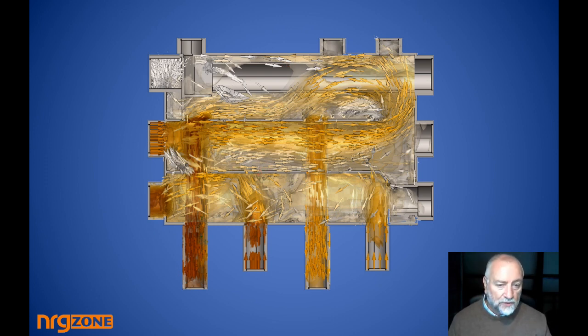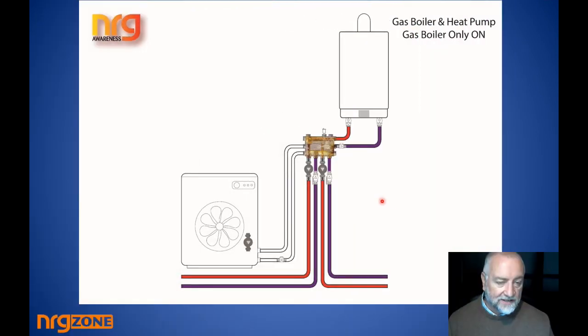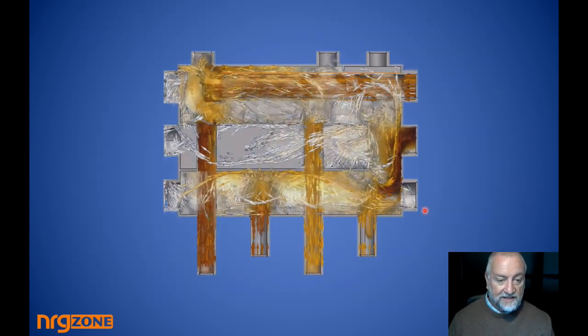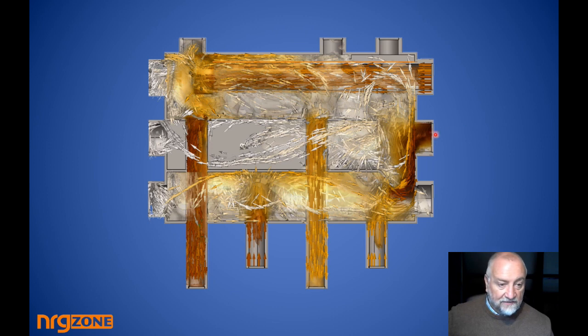If we go to the next scenario, the heat pump is turned off, and this time we are connecting to a gas boiler. But as I said to you, you don't have to take the return from the bottom chamber, and in this situation it makes more sense to take it from the middle one, because you'll see in a while why. If the cold water is being collected from the zones here, it's pulled up out of the middle chamber into the gas boiler.